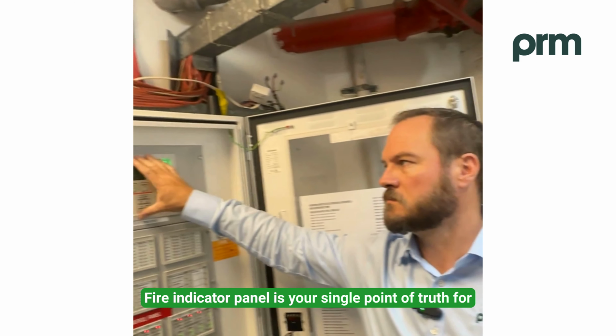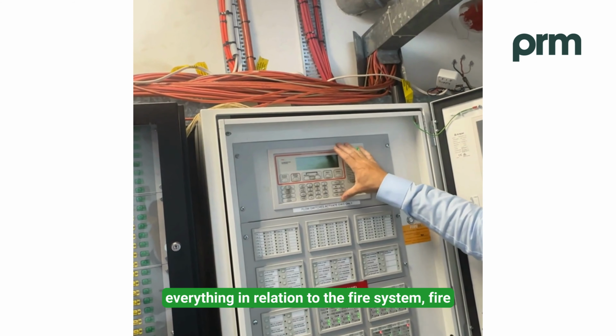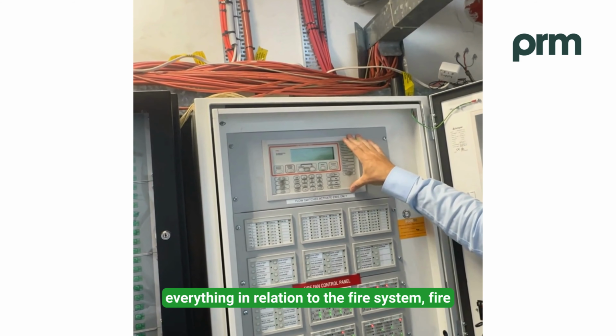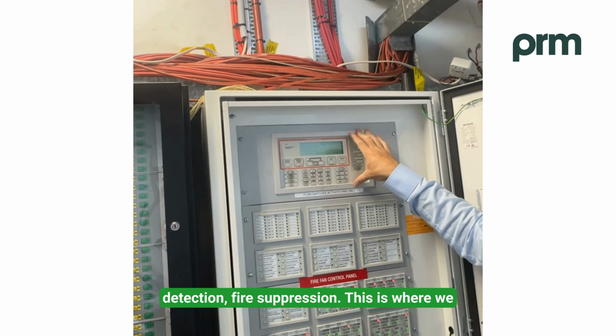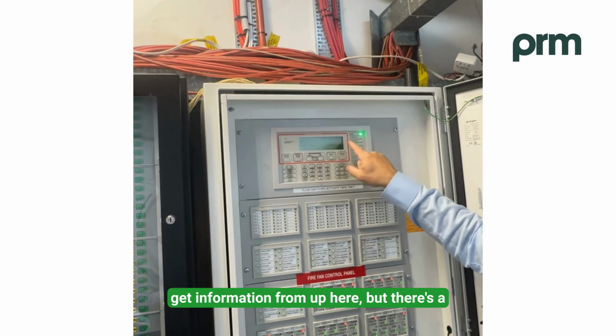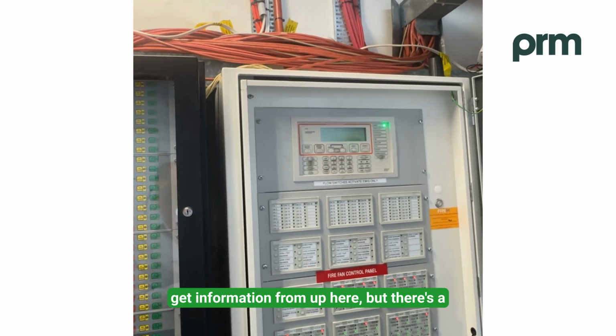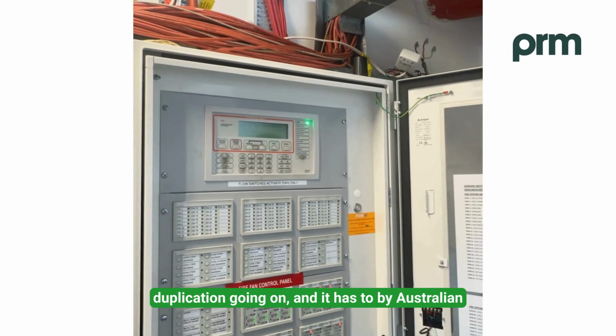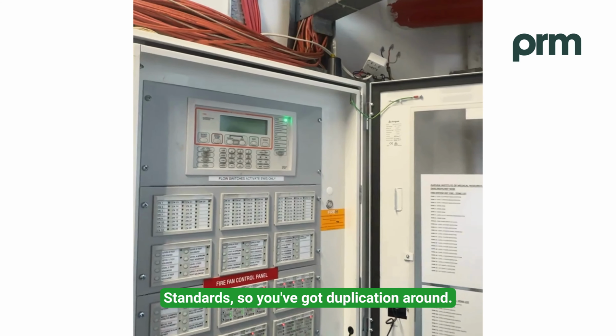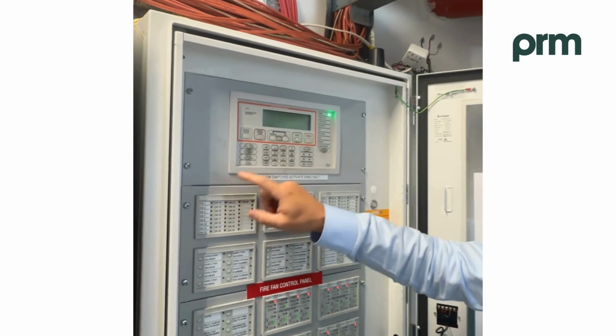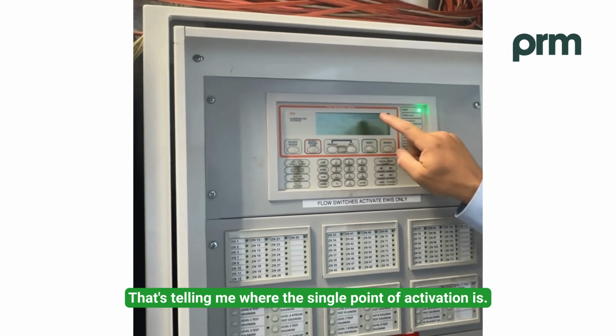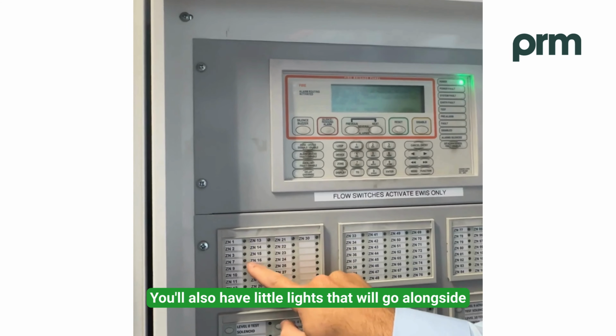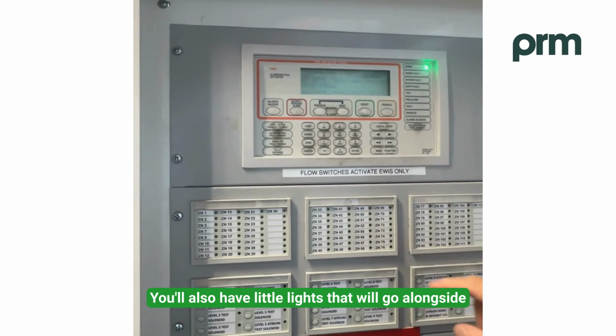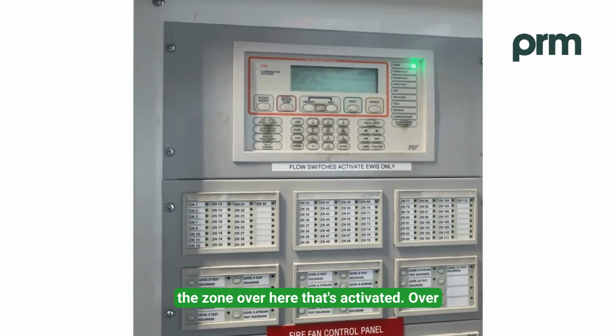Fire indicator panel is your single point of truth for everything in relation to the fire system, fire detection, fire suppression. This is where we get our information from up here. But there's a bit of duplication going on, and it has to by Australian standards. So you've got duplication around, that's telling me where the single point of activation is. You'll also have little lights that will go alongside the zone over here that's been activated.